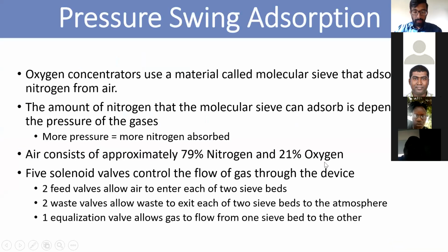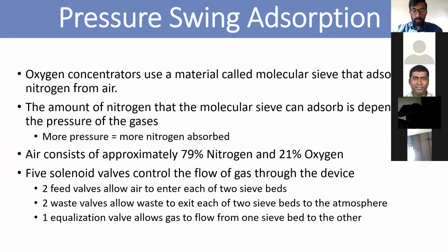Oxygen concentrator. So basically, when you talk about oxygen concentrator, you need to know about the material they use, called Sieve, to absorb nitrogen from air. The amount of nitrogen is more, so it's going to be absorbed by the Sieve absorber, depending on the pressure and the gas. So the more nitrogen being absorbed, the better the chances of oxygen going through. So that's how it works.